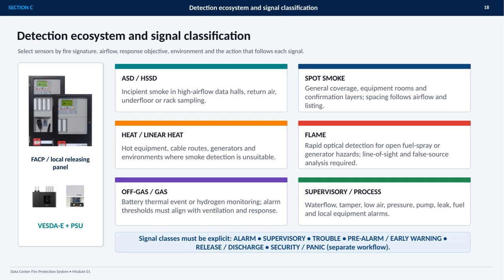Heat or linear heat detection is better suited to hot equipment, cable routes, generators, or areas where smoke detection is impractical. Flame detection supports rapid response to open fuel spray or generator hazards, but requires careful line of sight and false source analysis. Off-gas or gas detection can monitor battery thermal events or hydrogen, with thresholds coordinated with ventilation and response procedures.